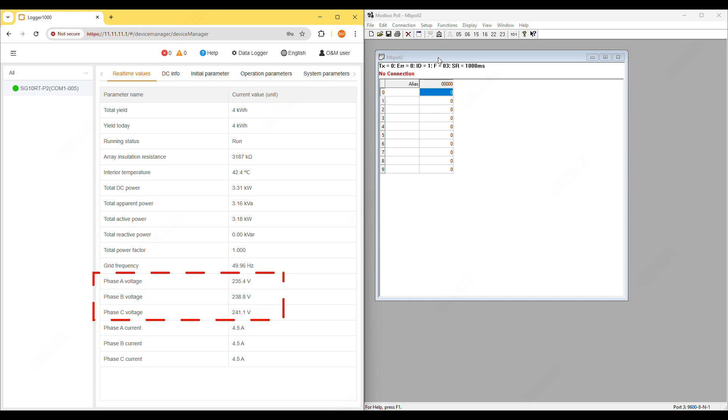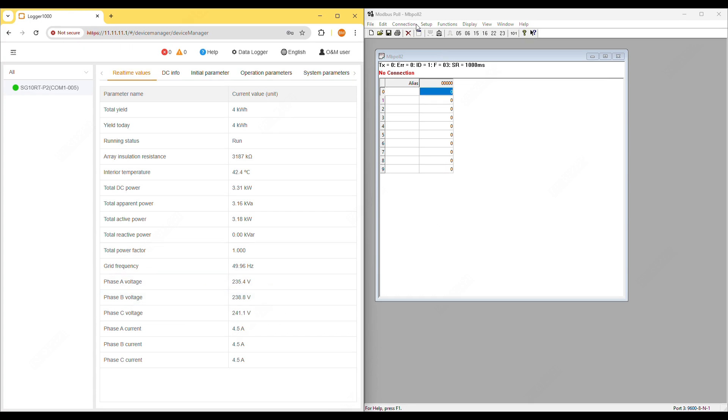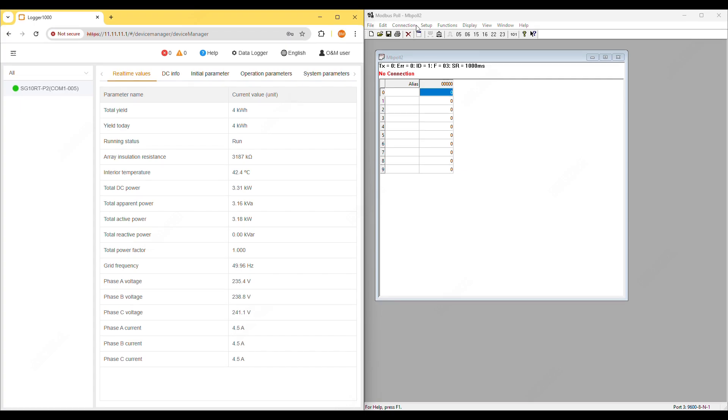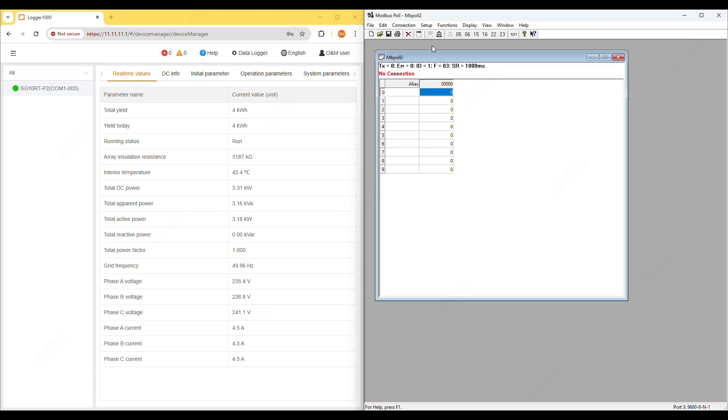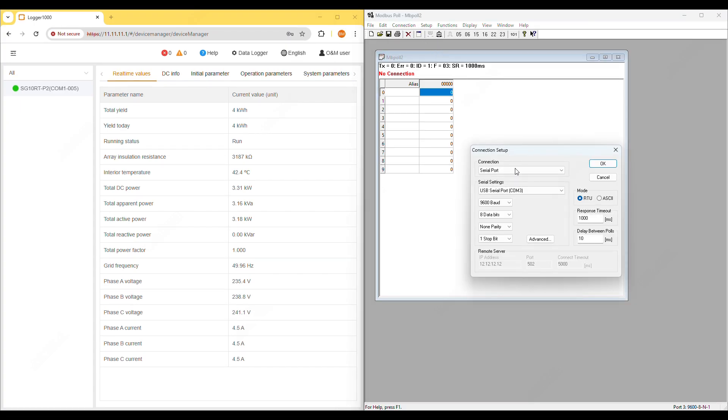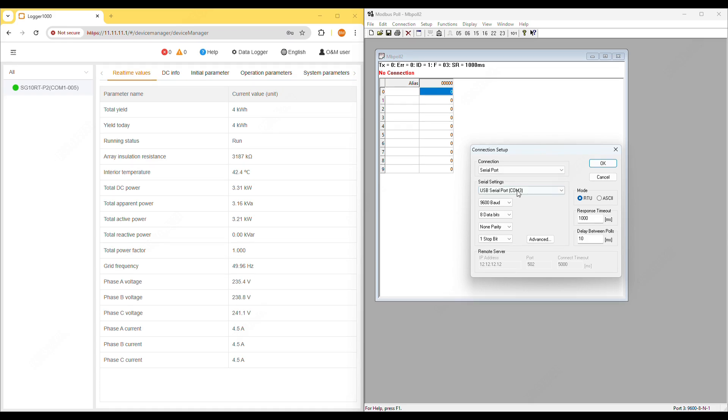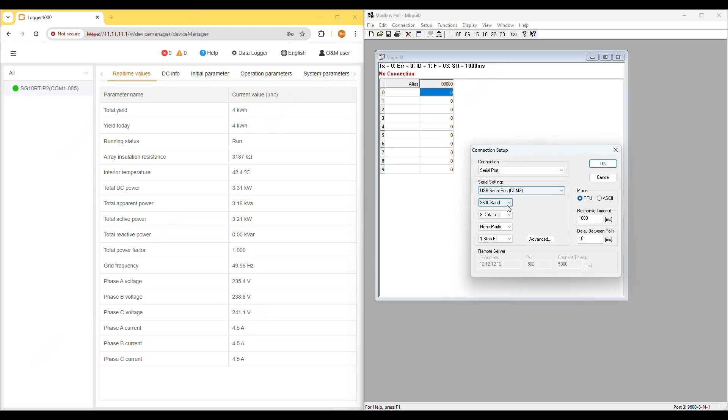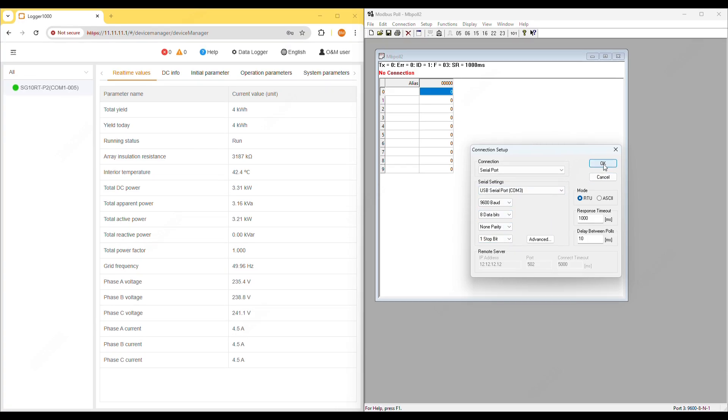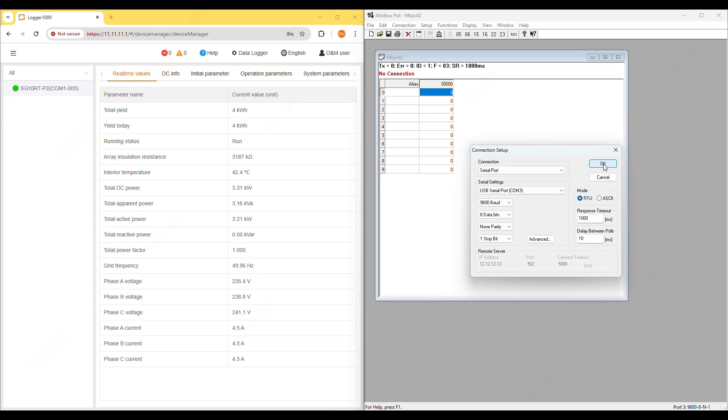Step 2, open Modbus poll and set up the connection. Go to connection, connect. The connection setup window will appear. Select serial port, choose the COM port that matches your USB RS485 adapter as detected by your computer. Set the baud rate, parity and stop bit to match the values we recorded earlier. Click OK.